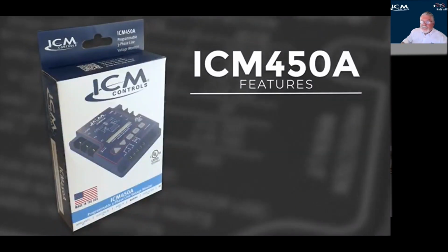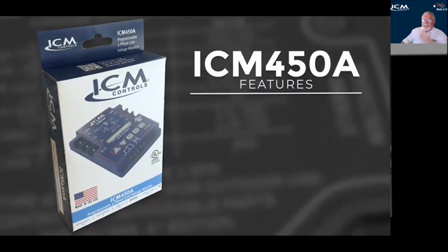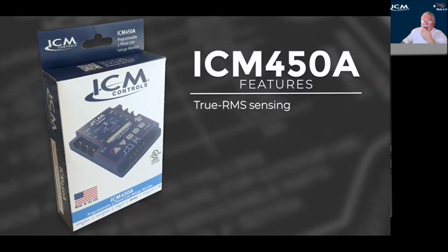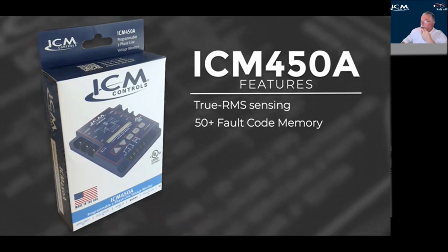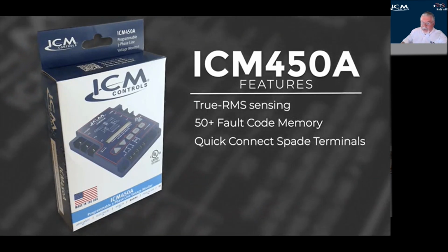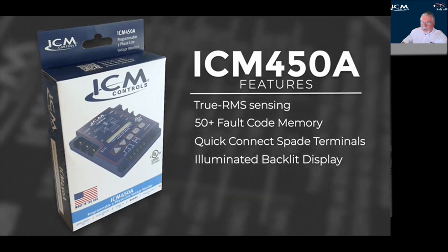Some of the upgrades over the previous model are it is now a true RMS sensing product. It has 50 fault codes memory. They put quarter-inch spade terminals on the unit now instead of screw terminals. It's got a backlit display so you can easily see it.